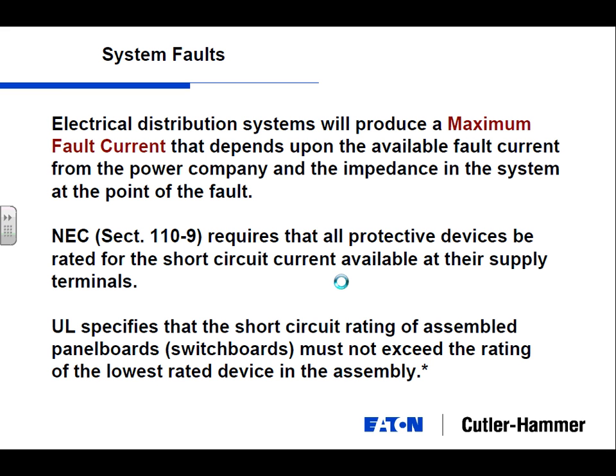So the impedance, the other part is the impedance of the system. And what is the distribution system? What is the largest thing that you think about when you're talking about impedance? Talking about cables. So once you come into that building, electricity's got to flow through all the different cables, all the different points in your facility. And for each foot of cable that you're moving, cable being impedance, you're lowering the fault current the farther you go into your distribution system.